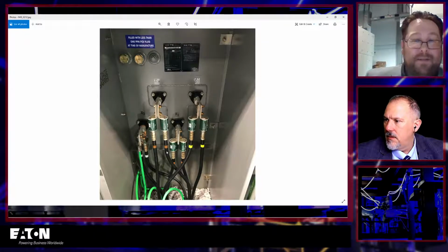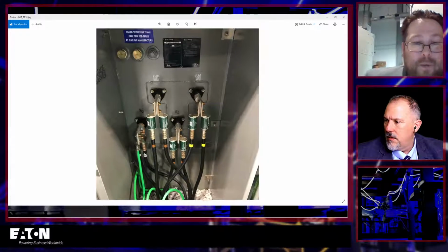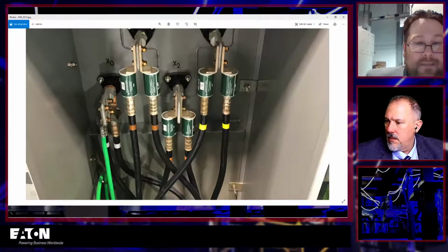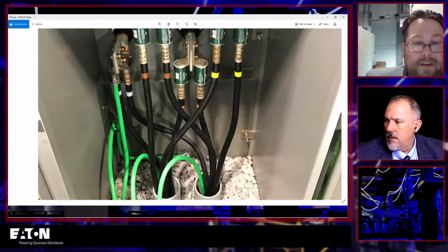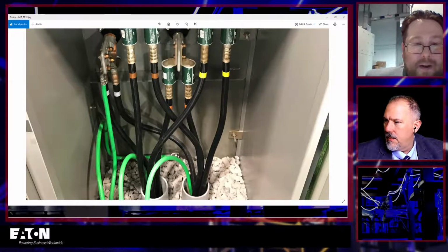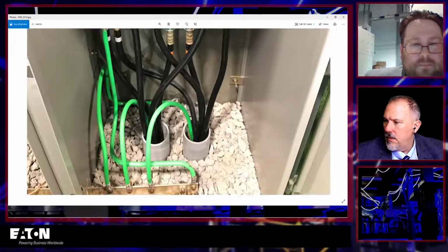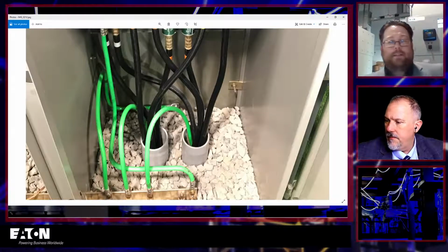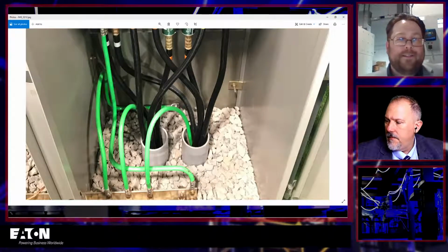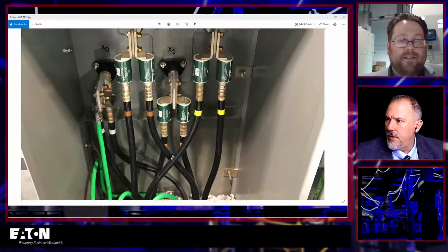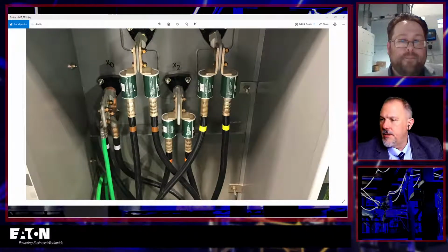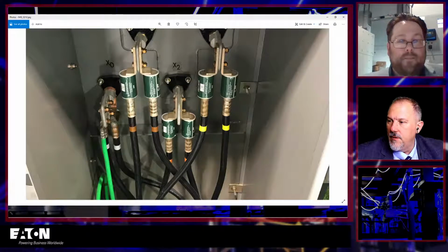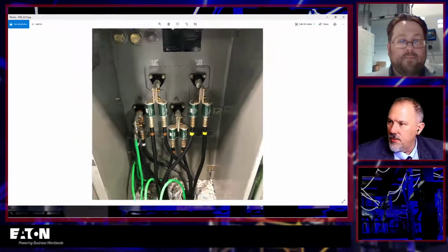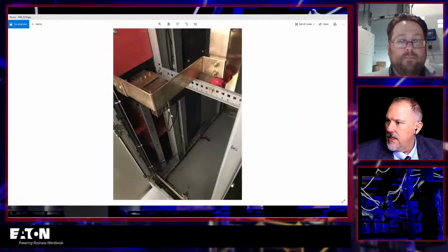And you see that neutral is on the far left, right there with that green cable. That's the bond that's bonding it to ground. Ultimately, there's a bus bar at the very bottom. I think it's in the picture, right here. Yeah, that's pretty cool. And those are your cable limiters. That's protecting the cable. And I have a video of him installing those, which we should do a program on cable limiters too one day.